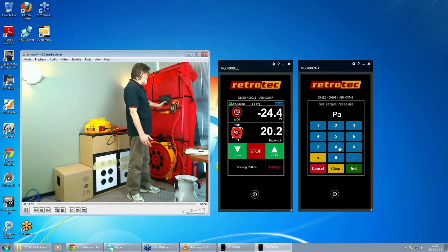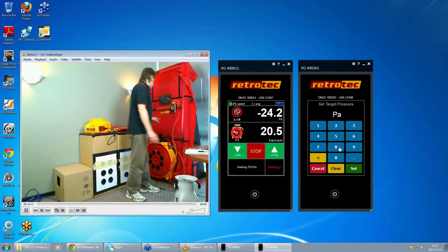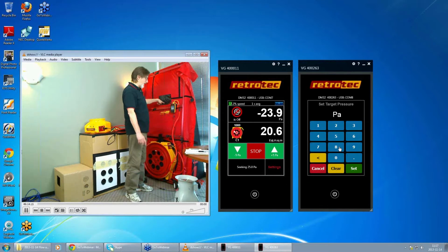You can do it at any pressure, but 25 pascals is a good pressure. And we've got an equivalent leakage area of 20 square inches. Now, you may not be able to see this, but if you look through this window, on the other side we've got one of the sliders set to a 4x4 hole, a 16 square inch hole. So we've got a 16 square inch hole, and we're leaking 20 square inches, which is the hole plus all the leakage around the fan and the cloth and this and that.